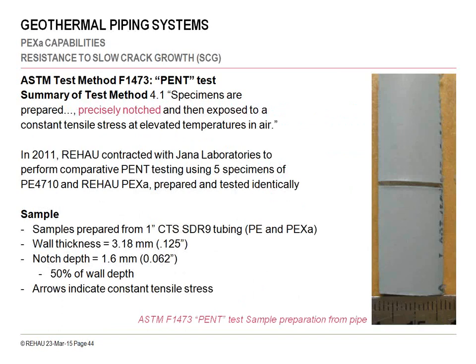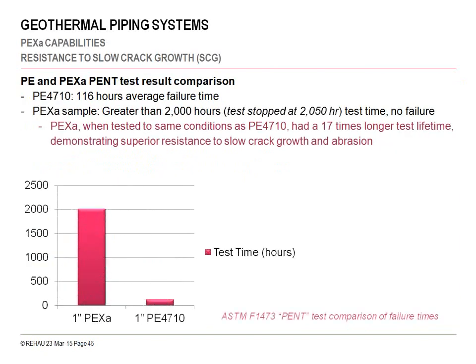RAUGEO submitted some samples of the PEX-A material to the testing lab. We were interested in seeing how we would perform in comparison to this new PE 4710 material that I mentioned. And again, with that weight force, we are stretching the pipe, and we are measuring in hours to 100% breakthrough, which would be a failure or leak in the piping system. So the PE 4710 failure time was 116 hours. That was an improvement of around 50 hours over the PE 3408 formulation. So there was an improvement. On the PEX-A material, after about 2,050 hours of testing time, it was decided to stop the test because there wasn't going to be a failure. But the purpose here is showing again the physical properties of PEX-A material, even against the newer formulation of HDPE, in this area of slow crack growth.